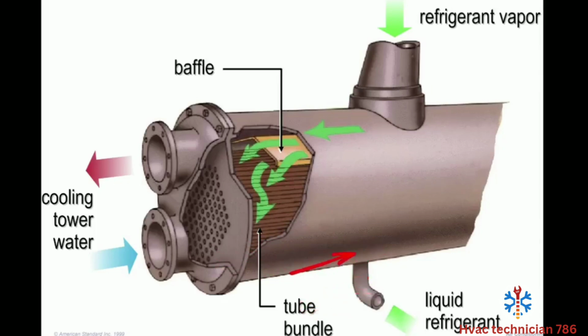These particular condensers don't take any kind of subcooling. It will be a fully saturated liquid refrigerant flowing out of here, but it will not have any form of subcooling. The point of this condenser is to allow the condensing gas to fully saturate down into a fully liquid state and drain out as it needs. There's nothing fancy going on here. This is a very basic setup.